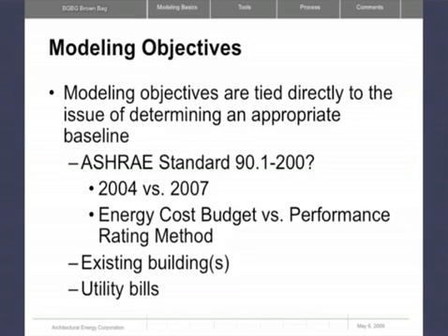If I don't want to do all that stuff, if I don't really want to put as much roof insulation in, I can use the energy cost budget method, where instead of putting in that much insulation, I might put in better windows, and then there's a procedure where you can trade those two off and get overall performance. That's often used for the code compliance kind of a path. You use the energy cost budget method, and instead of using the prescriptive approach as your target, you use something better than that, which in the City of Boulder's case might be 30% better.